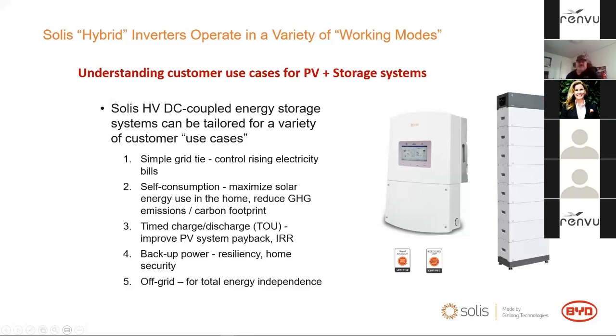We might want to stack a small BYD system there for later, and then a little bit larger one as we go forward. Setting up a grid tie system with a battery-ready grid tie inverter makes your homeowner a little more versatile, and maybe gives you an excuse to come back and sell them a battery later on. But generally, when you put in one of these inverters, the working mode that you're set to by default is self-consumption, where you are really reducing your greenhouse gas emissions and lowering your carbon footprint, because the battery will absorb any kilowatt hours that aren't being used by loads and fill itself up during the day.